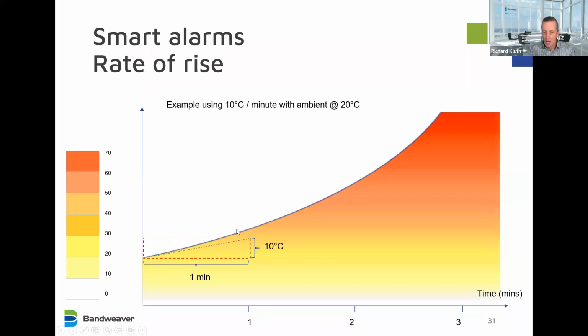The rate of rise allows you to trigger according to the change per minute. And one of the key benefits is it allows you to trigger much earlier. So if we imagine this is the temperature at a location in the event of a fire, we're starting at 20 degrees C and the temperature is gradually coming up. 10 degrees C per minute is a typical range. So if this is time along here, this is a minute, this is 10 degrees C. We're actually hitting the 10 degrees C at this point, and so you're triggering here at 30 degrees C, in under a minute. So it's a fast trigger.